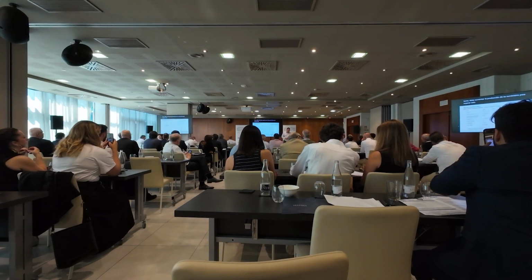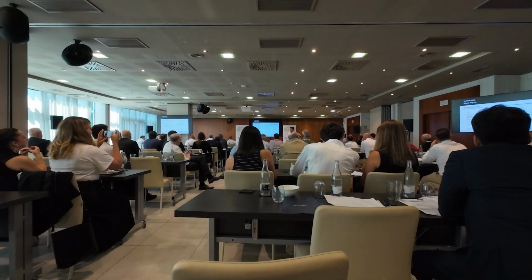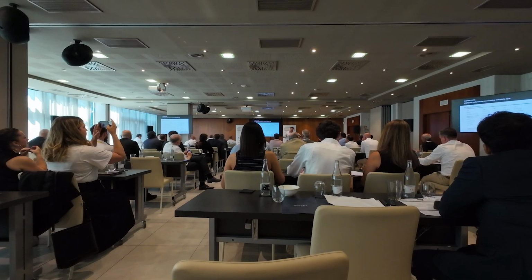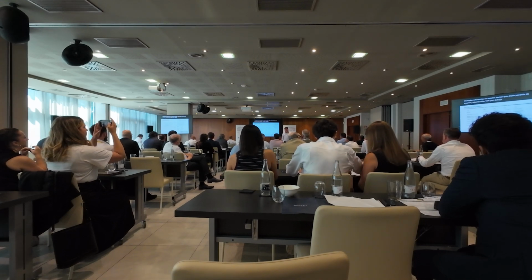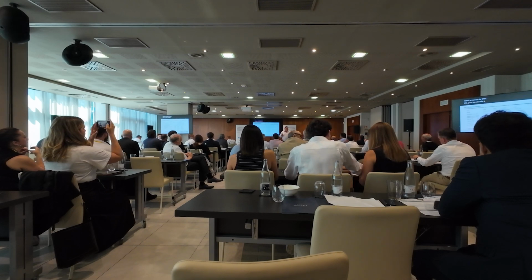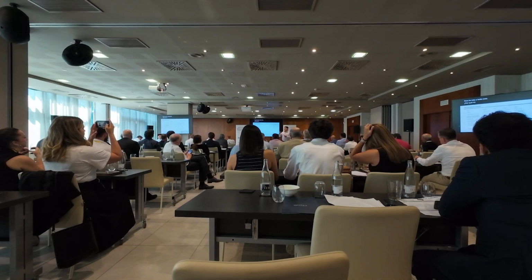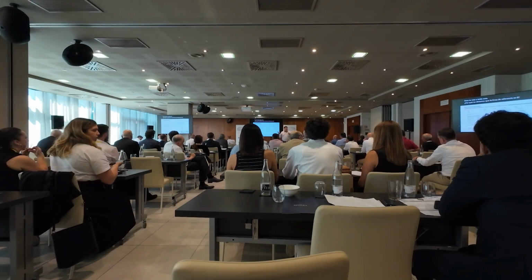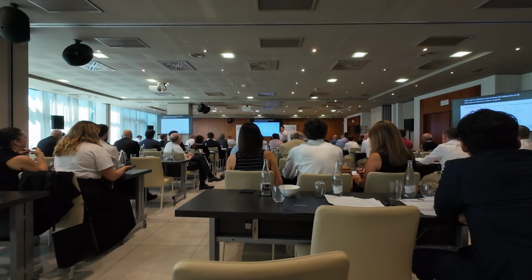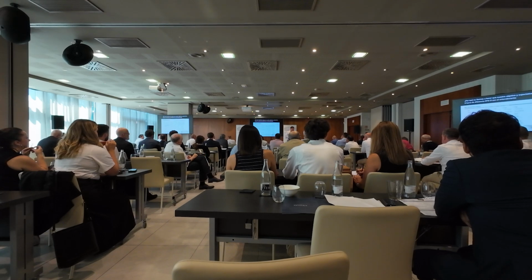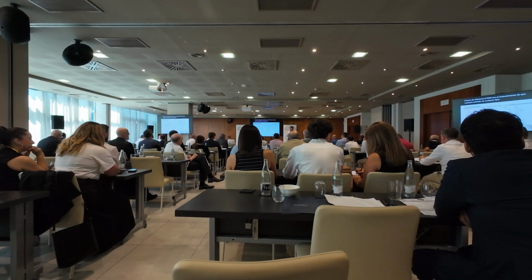Now there is multiple references in our industry that say, pressure loss in distribution under 10%, or under 10 psi, or under 5 psi. But I challenge you all this. Why wouldn't we say that the reference line is 0? Why wouldn't we make our goal and expectation 0 bar difference, 0 PSID, with an understanding that any loss whatsoever is waste?